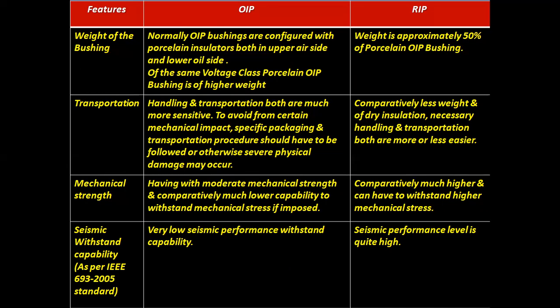Transportation. Handling and transportation are both much more sensitive. To avoid certain mechanical impact, specific packaging and transportation procedures should be followed, or otherwise severe physical damage may happen. With comparatively less weight in the case of RIP bushings of dry insulation, handling and transportation are both more or less easier. Mechanical strength: OIP has moderate mechanical strength and comparatively much lower capability to withstand mechanical stress if imposed. But in the case of RIP bushings, it is comparatively much higher and they can withstand higher mechanical stress.